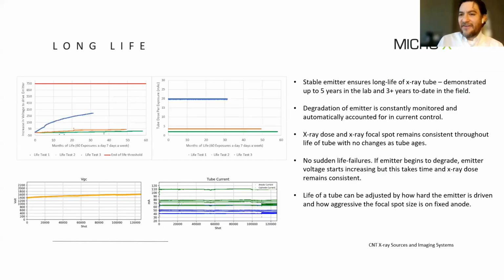The other advantage of the carbon nanotubes is long life. So the emitter itself, as I talked about before, is very stable, and we can control the life of the emitter. The emitter itself degrades or changes very consistently depending on how hard you run it. So in these ones, we're kind of looking at life testing, not just of the emitter, but of the entire X-ray tube, and taking multiple exposures at different life. So the green and the orange are typical use, and the blue is the most aggressive use of that tube consistently. So as you can see, even with the most aggressive use of that tube, the tube is not likely to degrade in 5 years.